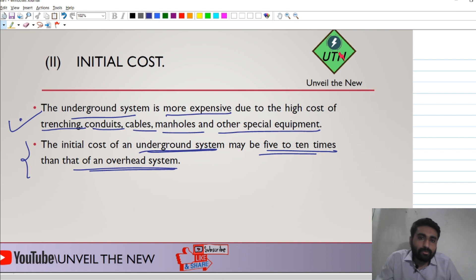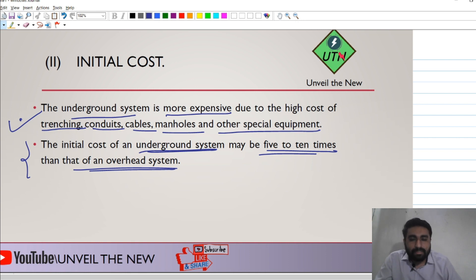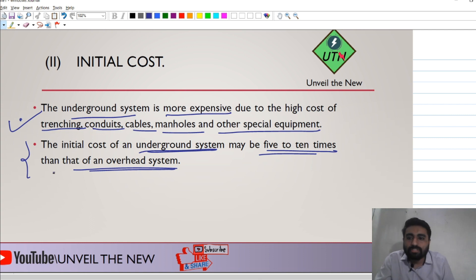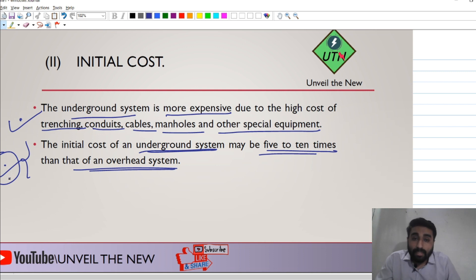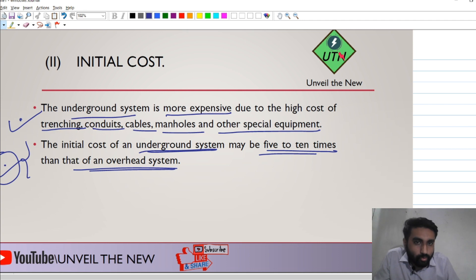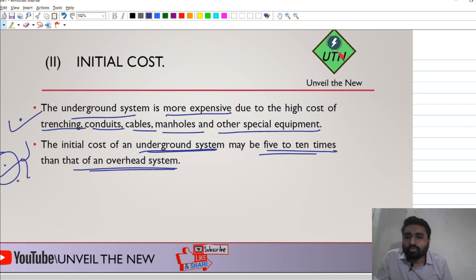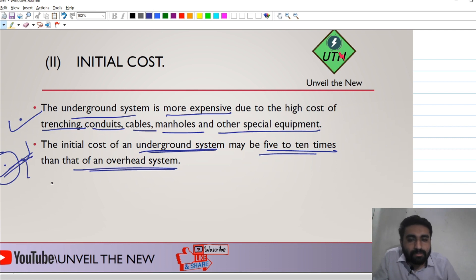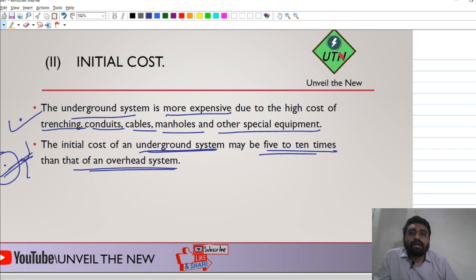The initial cost of the underground system may be five to ten times that of the overhead system. The initial cost is a very important parameter, and that is why in India, which mostly uses overhead systems, this factor is heavily considered.